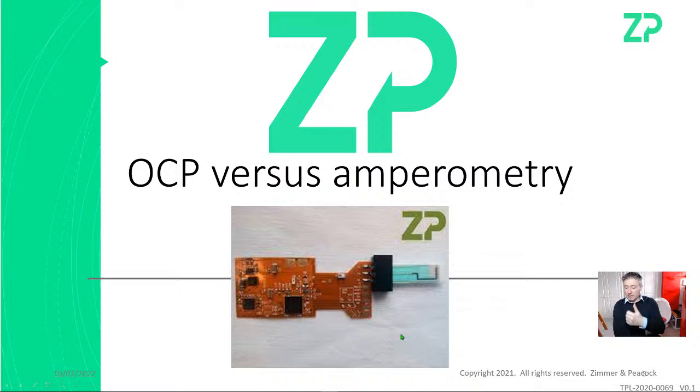And as I say, it comes in two modes: OCP, open circuit potential, is used with our ion selective electrodes: phosphate, potassium, sodium, nitrate, pH, calcium, things that are generally ions. So I just listed out a bunch of ions there. Now there's another mode, which is amperometry, and that's for measuring mostly the enzyme-based sensors.